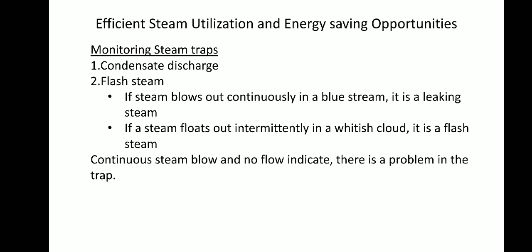The second one is flash steam. This shall not be mistaken for a steam leak through the trap. The user sometimes gets confused between flash steam and leaking steam. The flash steam and leaking steam can be approximately identified as follows. First, if steam blows out continuously in a blue stream, it is leaking steam. If steam floats out intermittently in a whitish cloud, it is flash steam. Continuous steam blow and no flow indicate there is a problem in a trap. Then immediately we can check.